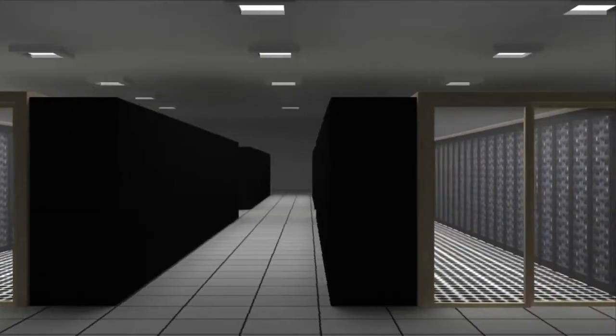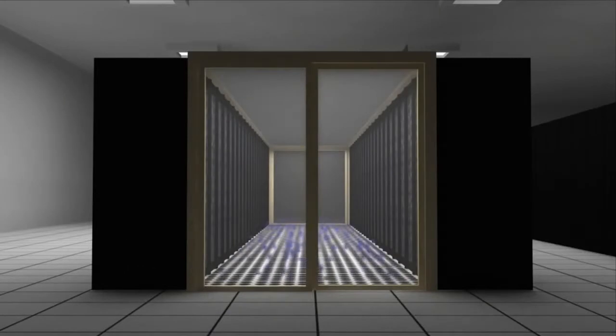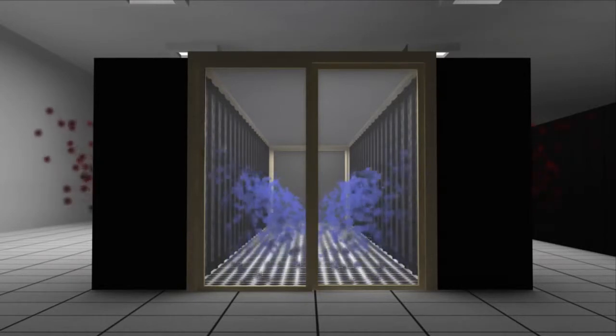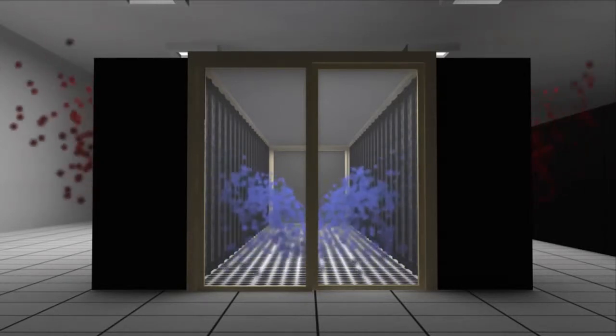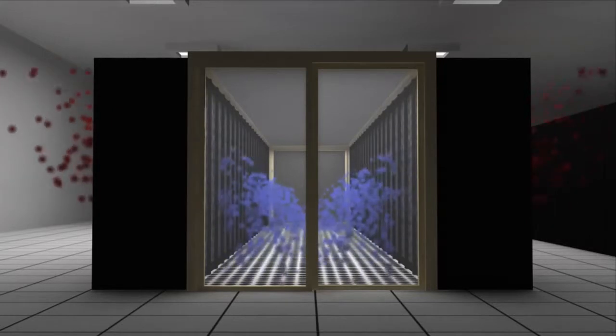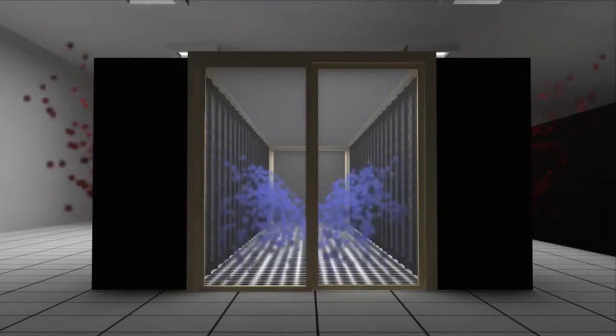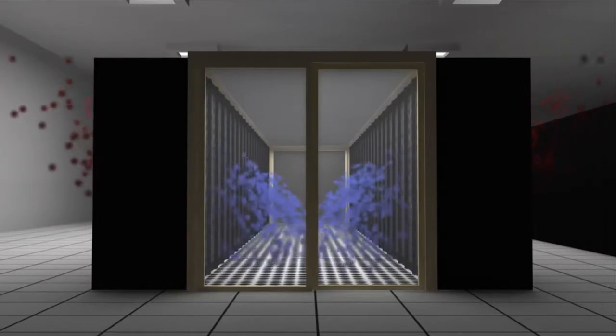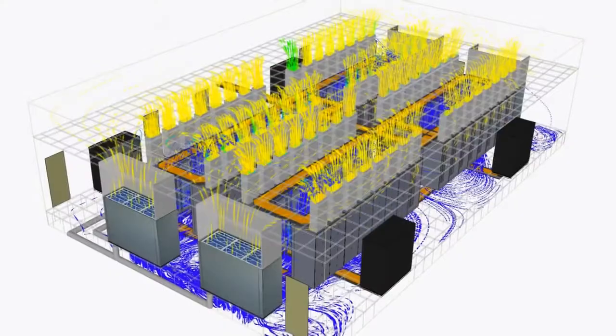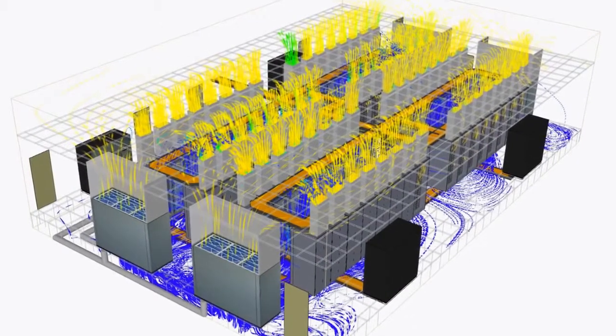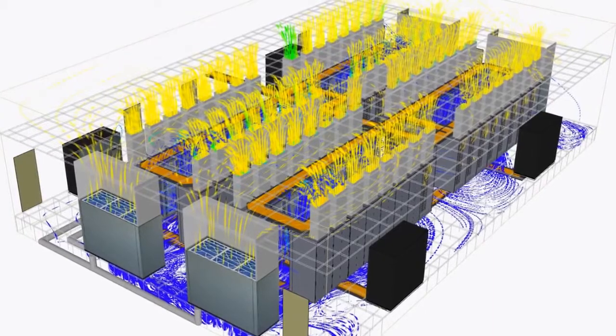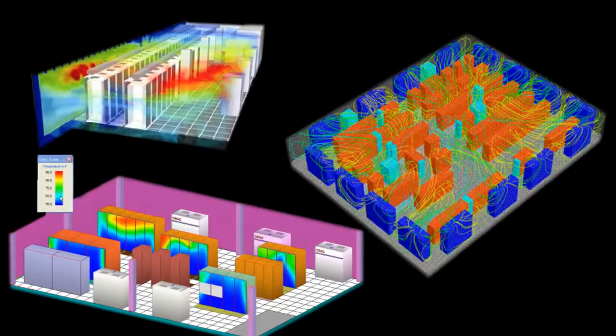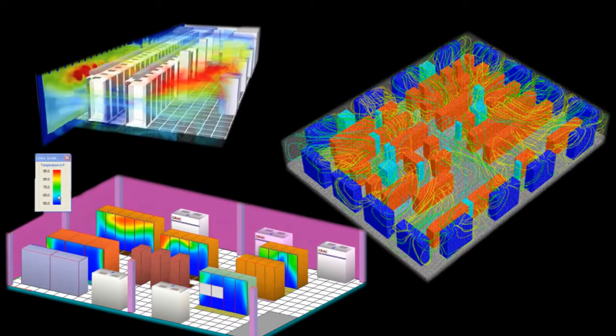In order to improve the efficiency of the cooling system, the area of the cold aisle is contained so that the cold air does not mix with the hot air in the rest of the room, and the entire data center acts as a hot air plenum. Although the temperature of the room rises, the air reaching the servers is cool, thus bringing in more efficiency. A CFD or computational fluid dynamics analysis is done to measure environmental conditions including airflow, temperature, humidity, pressure differentials and other parameters of interest such as power, intrusion detection and equipment failure notification.